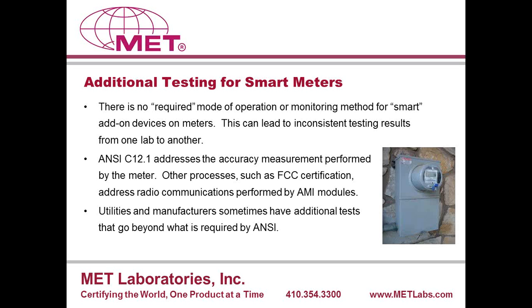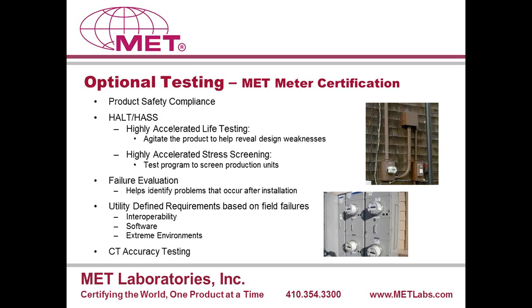There is, of course, additional testing for smart meters that goes beyond the ANSI standards. The wireless modules, for example, need to be tested for FCC certifications and verifications. There may be product safety type tests that need to be performed on sub-modules that are installed within a metering product. There could also be issues that either the manufacturer is hearing back from field installs or utilities are seeing in the field, where you're trying to nail down what might be going on, and something is causing a problem that goes beyond what is required by the current ANSI C12 standard.